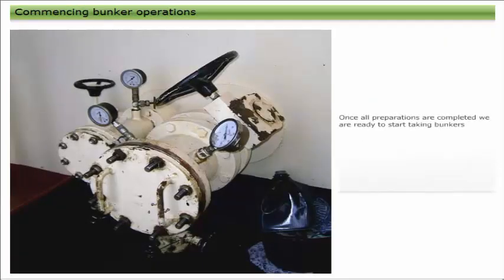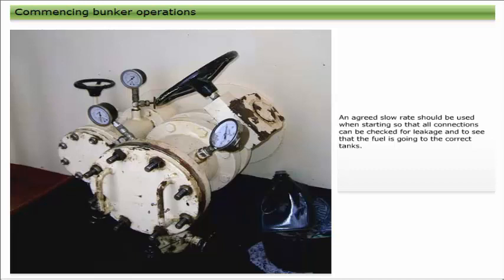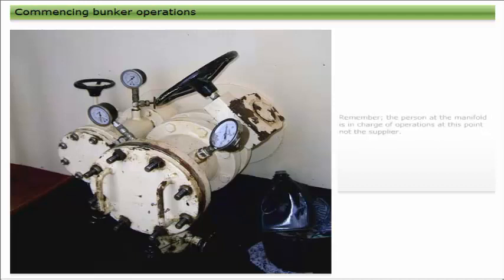Once all preparations are completed, we are ready to start taking bunkers. If there are any problems with hose connections or valve settings, they will likely show up at the very beginning of the operation. An agreed slow rate should be used when starting so that all connections can be checked for leakage and to verify that the fuel is going to the correct tanks. Only when you are sure that everything is as it should be should the rate be increased up to the agreed maximum rate. Remember: the person at the manifold is in charge of operations at this point, not the supplier.